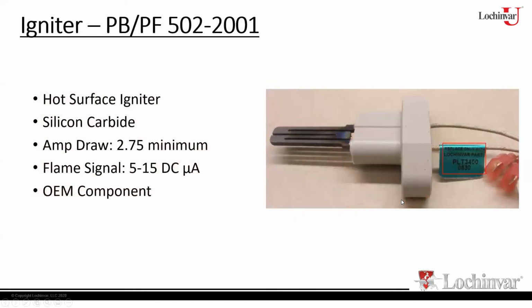All right. Now, how do we ignite this gas air mixture? All right. So our smaller models from 500,000 to 2 million, we're going to stick with our standard HSI, our hot surface igniter. All right. Any product from 400,000 BTUs and larger has to use a proven pilot ignition system. So this can be a proven hot surface igniter. It could be a direct spark ignition system with the flame rod. It could be a standing pilot with a thermocouple. There's different things that you could choose there. For the 500 through the 2 million, because of when it was developed, we went with the HSI. This is what we had available, and this is what we stuck with.